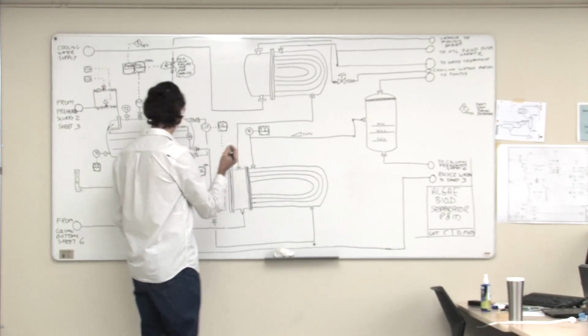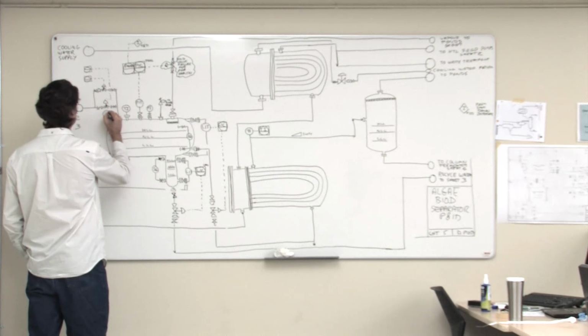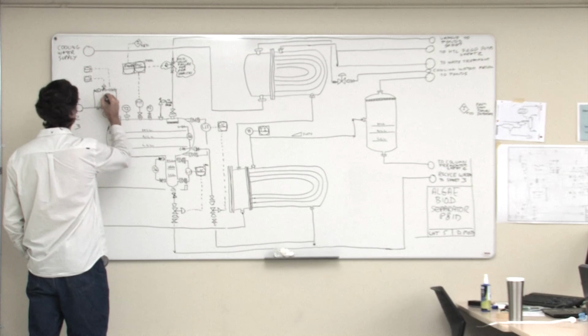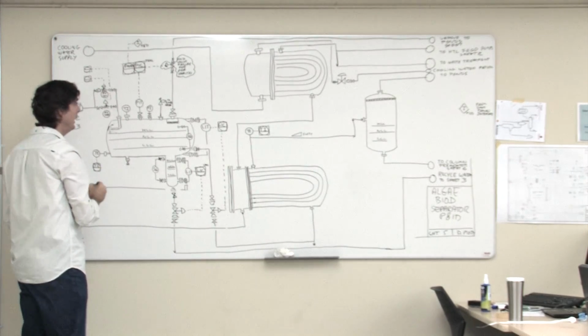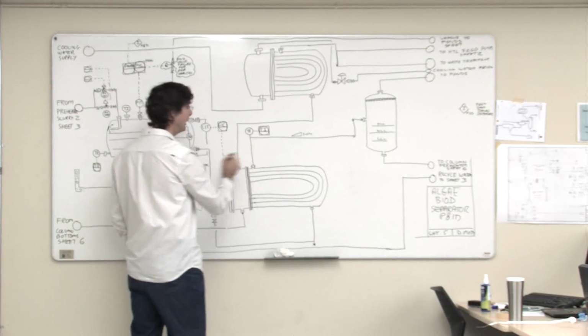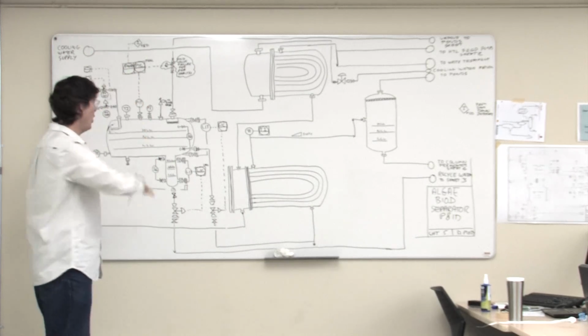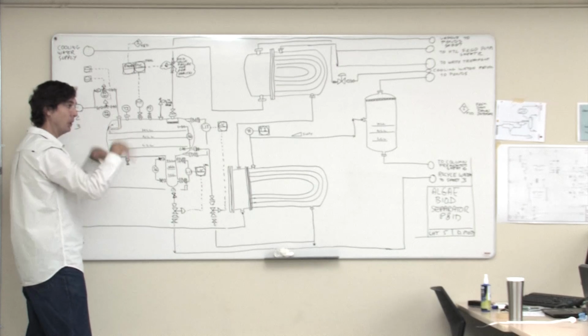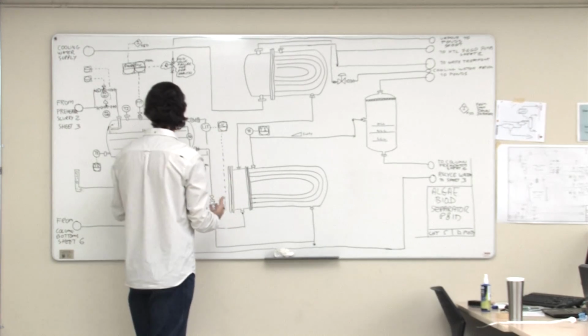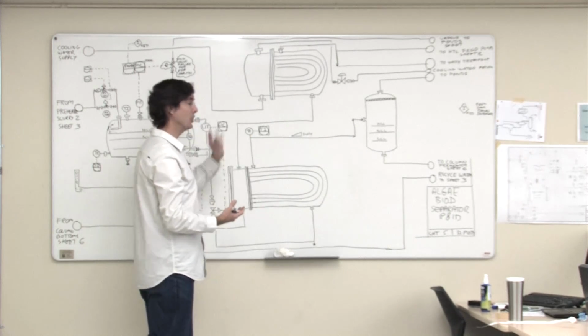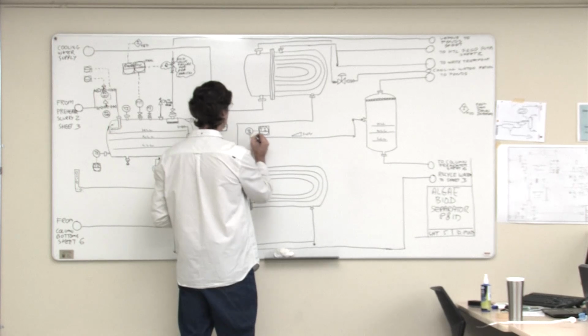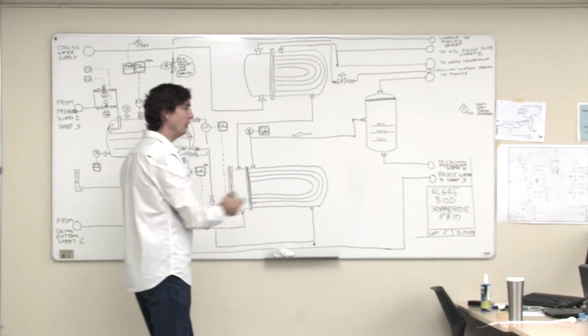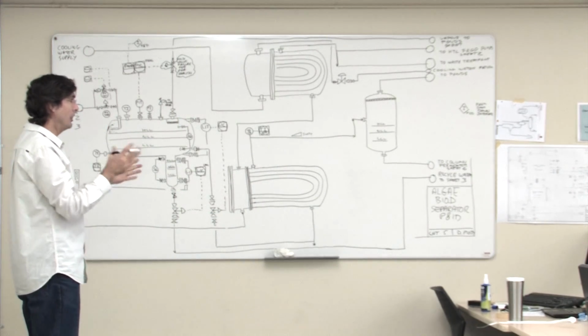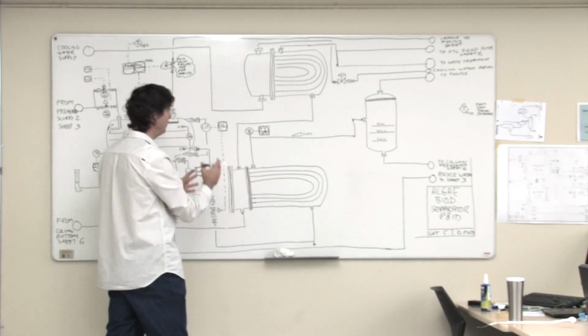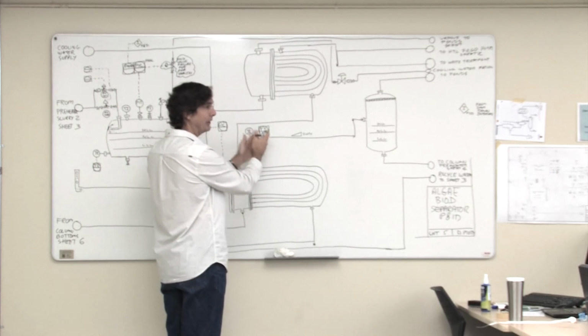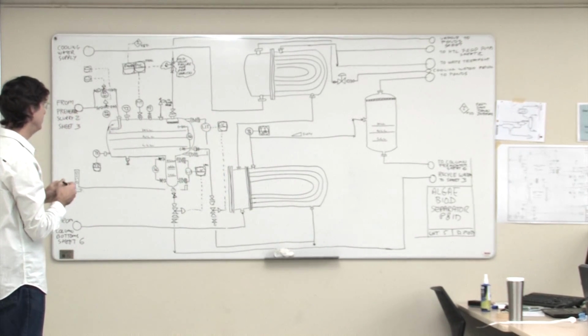Every one of these instruments is going to be given a number. So this is a flow valve, FV 100, and this is FV 101, something like that. The level transmitters are given numbers, the TEs are given numbers, and then they create a big spreadsheet with all the instrument tags. All this field stuff has to get purchased, so they need to know to purchase the TE, giving it a number so they can track and purchase it. Let's call this TE 150, and this is TI 150. It's a way to track all the tags and instruments, and for people to understand how much work is required for design and construction. They split it up so people know they've got to buy a TE, what it is, and that software configuration has to be done - just for design and construction purposes.